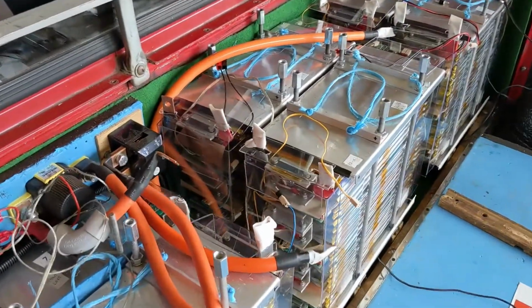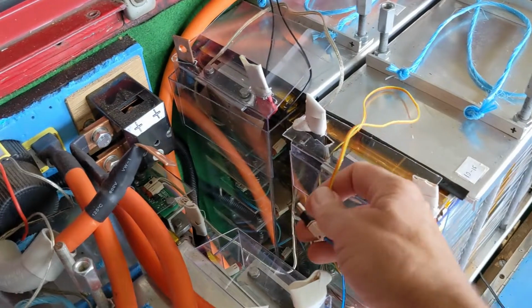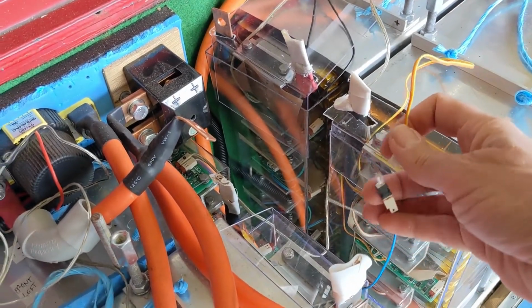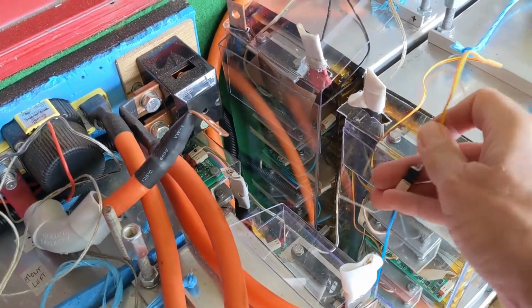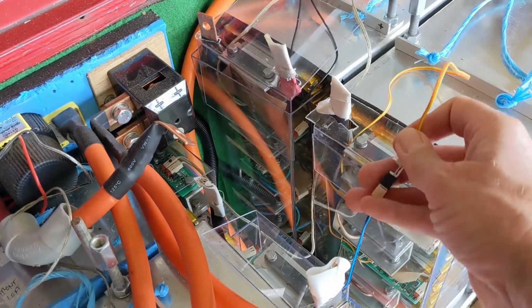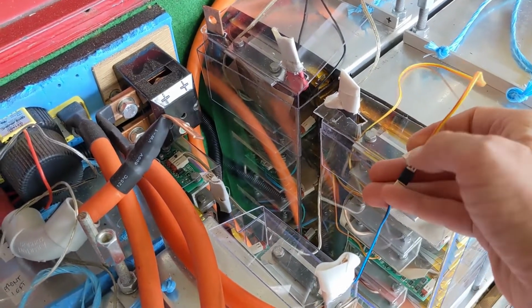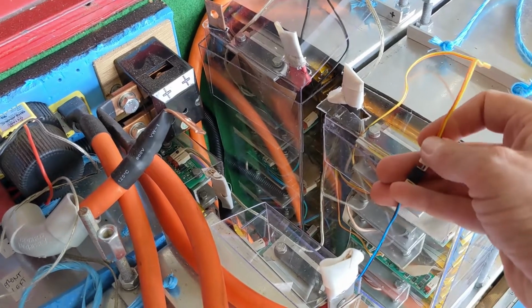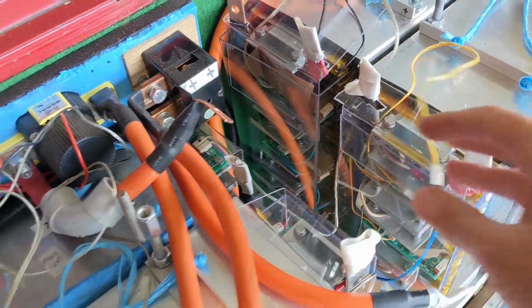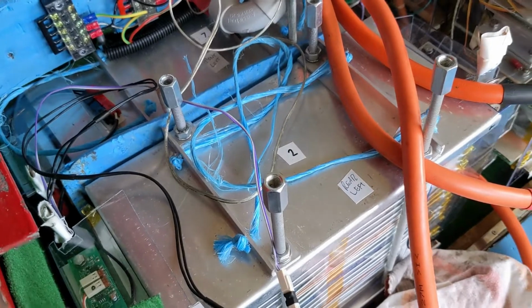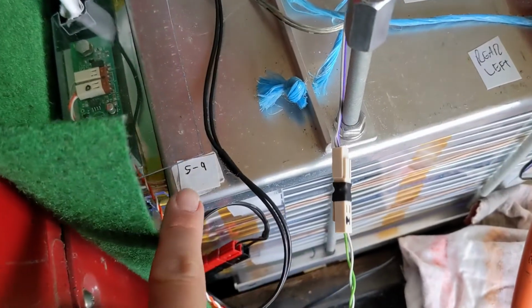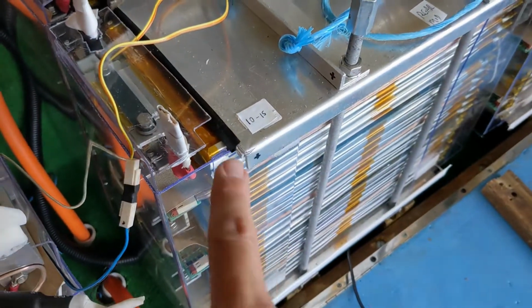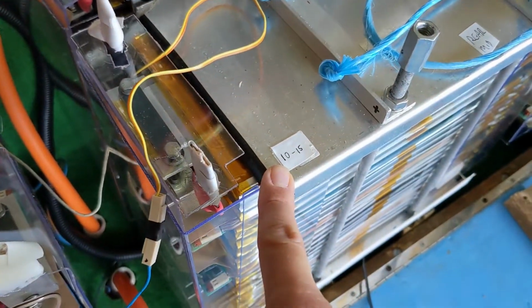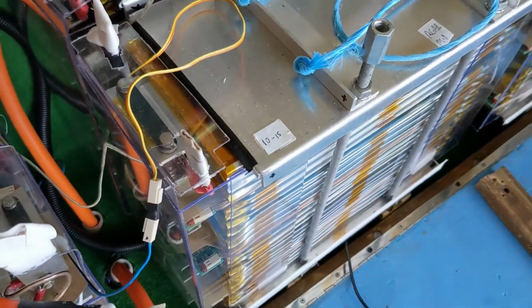Why you want to do this is in case there's a fault, a broken wire, or one of the modules stops working - it's handy to know which one it is. So while it's working, I plug that in, and I go through and label what the cells are. So here I've got 5 to 9, 10 to 15, etc. If I had cell number 14 complaining, I'd know it's in this bank.